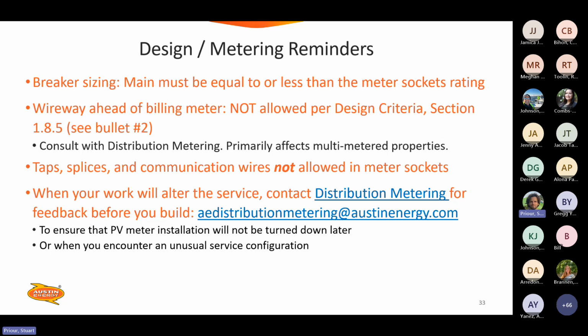you'll need to consult with distribution metering. And this primarily affects multi-metered properties, so you won't likely see it in 1 and 2 family dwellings. Also, taps, splices, and communication wires are not allowed in meter sockets. So we don't want to have a situation where there's service required by the contractor inside of our meter cans. The only thing that should go inside of a meter can are the power conductors that are actually being metered. Other than that, you've got to reroute any other conductors to not go through the meter can.